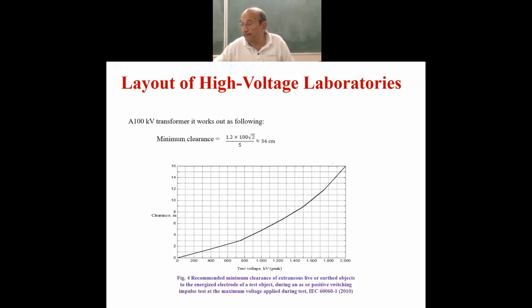Let's go to the next slide. Some guidelines for clearance: people have been working to optimize the safety distance for clearance anywhere, let it be in the laboratory, the substation, or electric traction. The safe clearance distance to a grounded object is a very wide subject, and people have been experimenting to optimize it, even now, because the clearance requirement may differ for different equipment and different weather conditions. People have been working on this for a very long time.